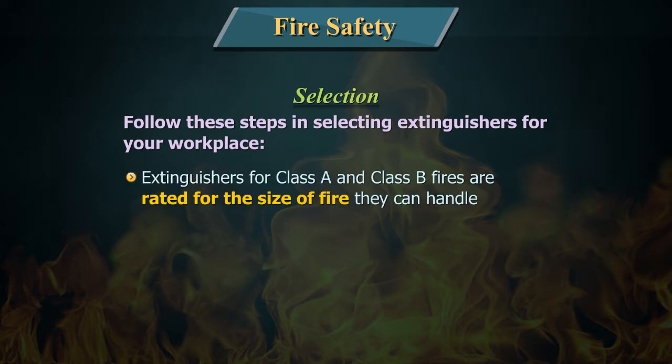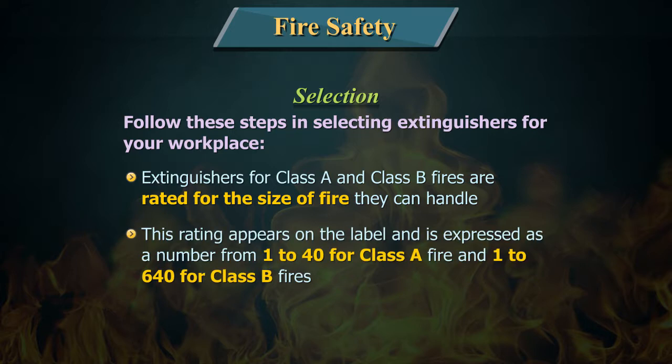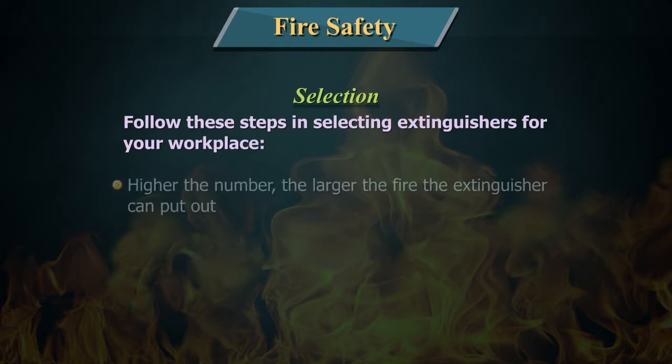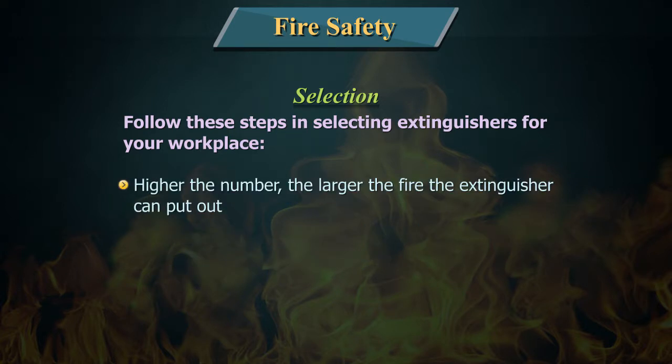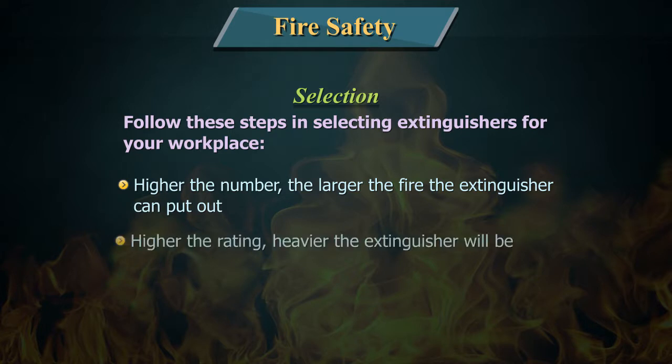Extinguishers for Class A and Class B fires are rated for the size of fire they can handle. This rating appears on the label and is expressed as a number from 1 to 40 for Class A fires and 1 to 640 for Class B fires. The higher the number, the larger the fire the extinguisher can put out. However, the higher the rating, the heavier the extinguisher will be.